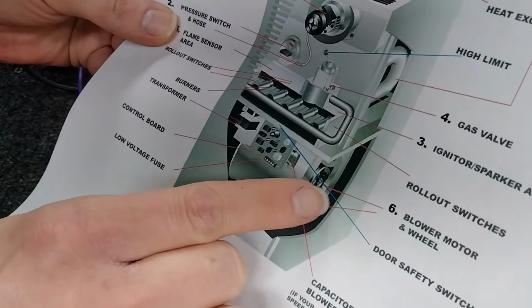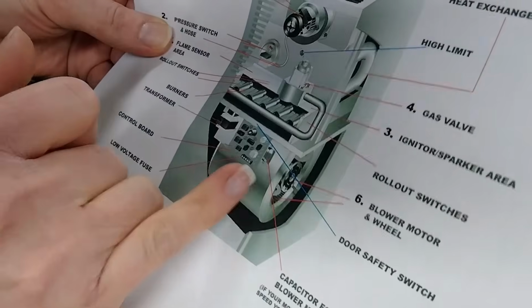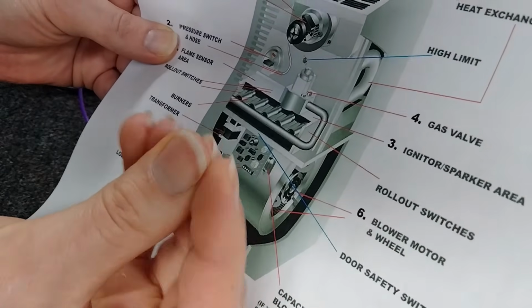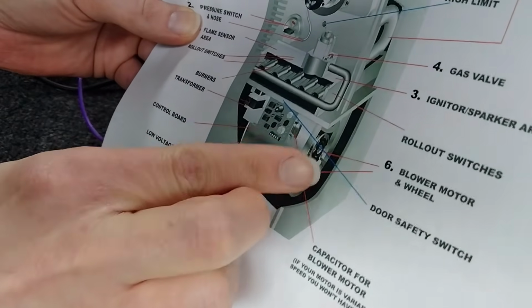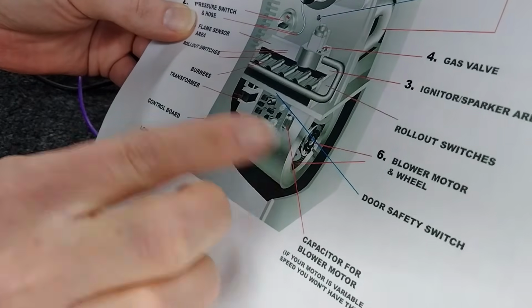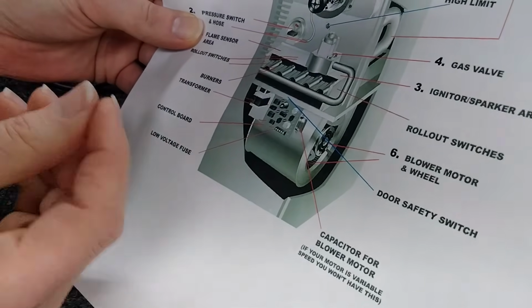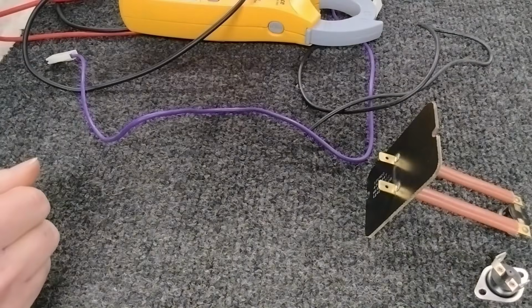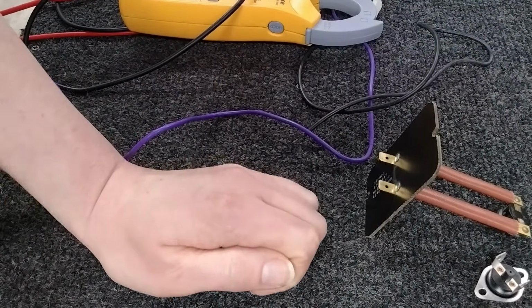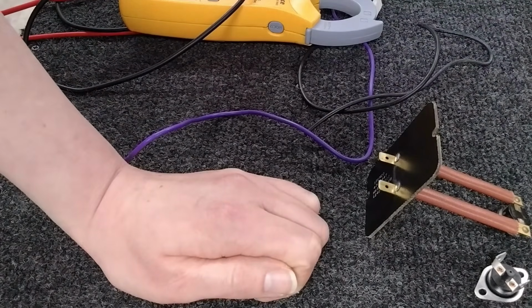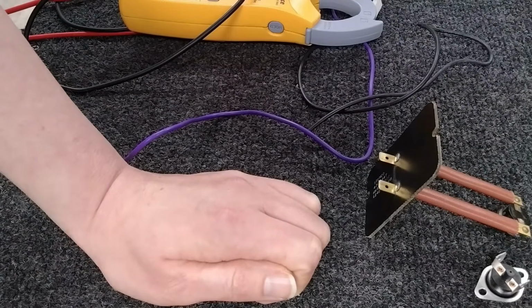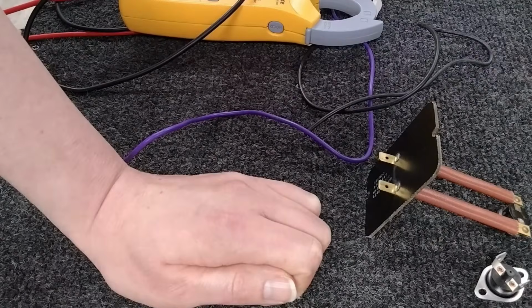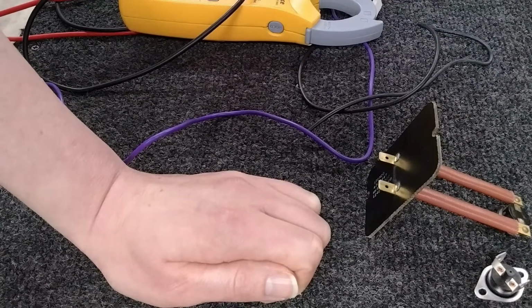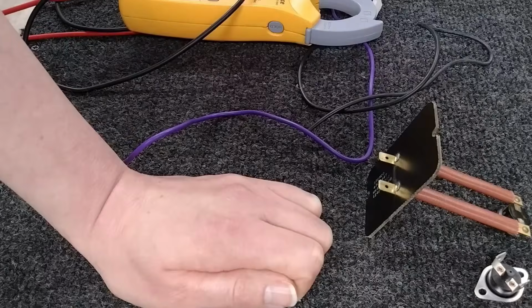If you're seeing a lot of crud in your motor, kind of around it, some smudge, dirt, hair, lint, gross stuff, or in the blower wheel or here, then that's a really good indication you need to clean it. Also on your filters, if you're noticing you're having to replace your filters more often than usual, or if they're getting dirty much faster than you think they should be, it's probably time to check on those evaporator coils. Unlike your outdoor coils, your indoor coils can be cleaned once every few years.